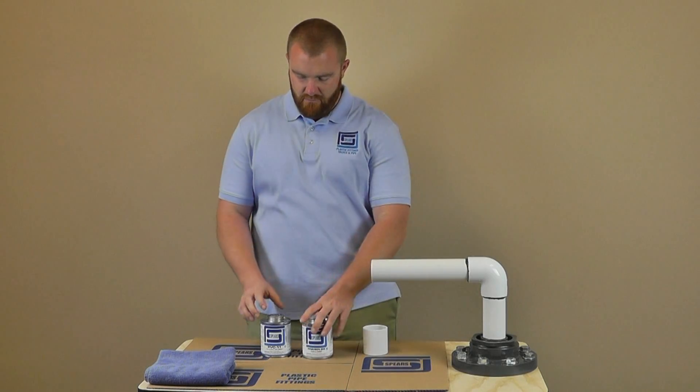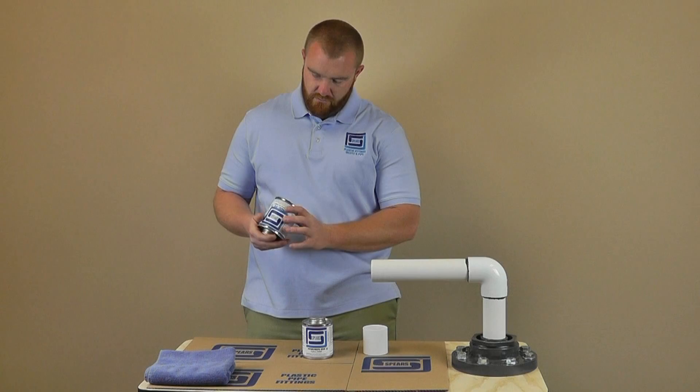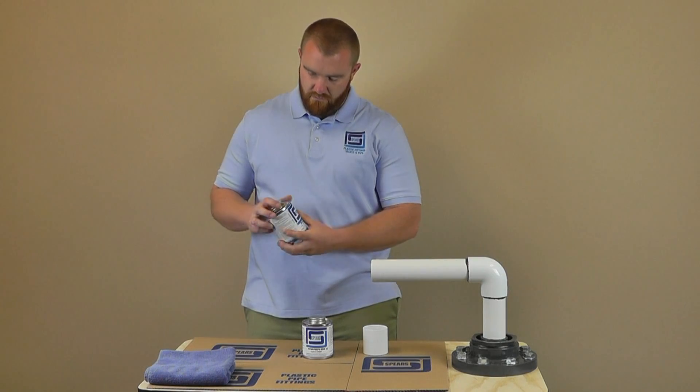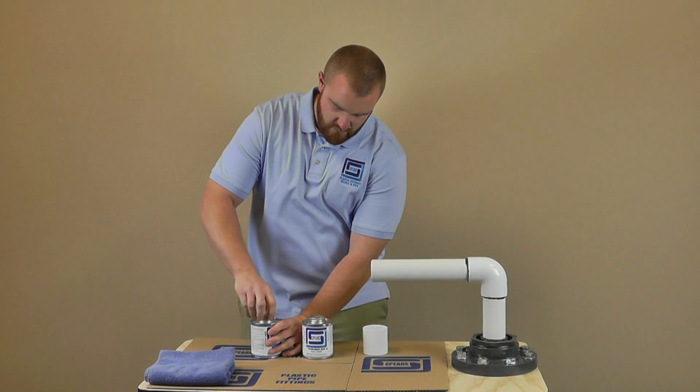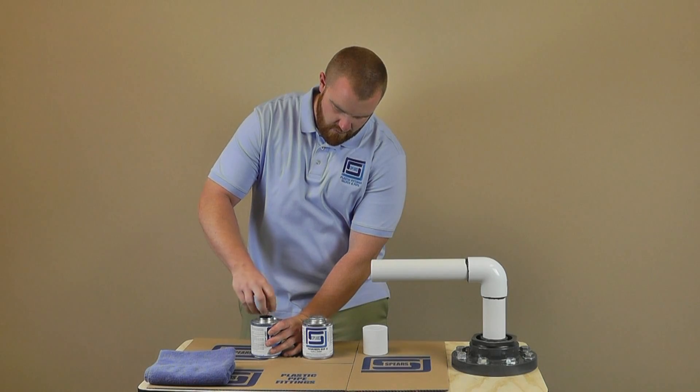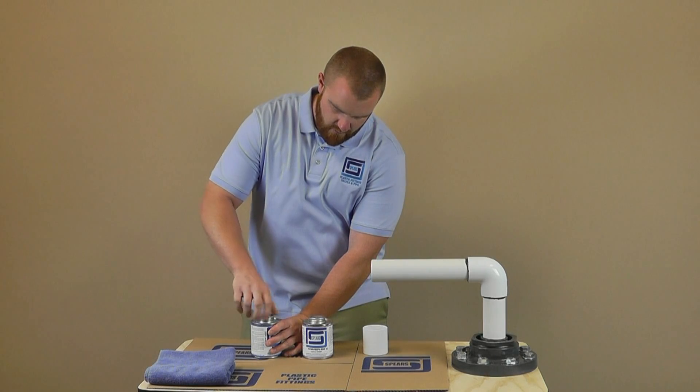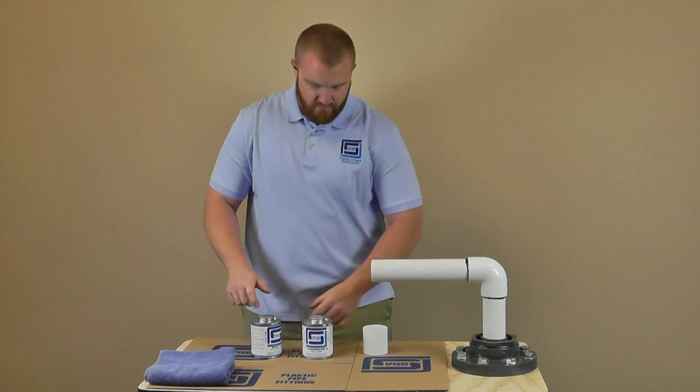Check expiration dates on both primer and cement. Spears PVC solvent cements and primers have a 3-year shelf life. Do not use primer or cement that is 3 years older than the date on the bottom of the can. While checking the date, make sure to shake or stir the solvent cement thoroughly. Do not use if dried or gelled.